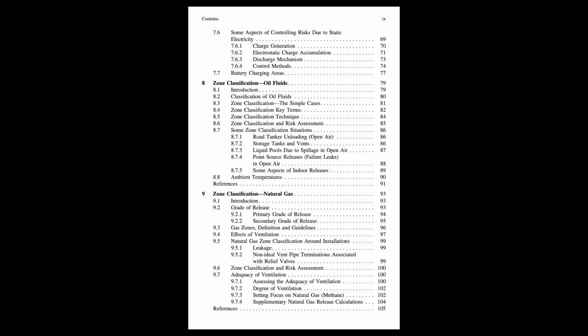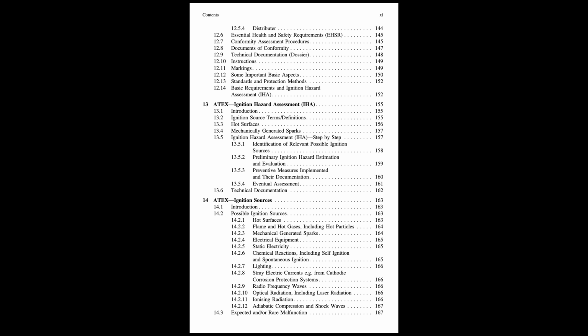Ah, good point. No, ventilation does not affect the grade of release itself. The grade is purely about the source characteristics, how often it leaks. However, ventilation has a massive impact on the extent or size of the resulting hazardous zone. So good ventilation shrinks the zone.